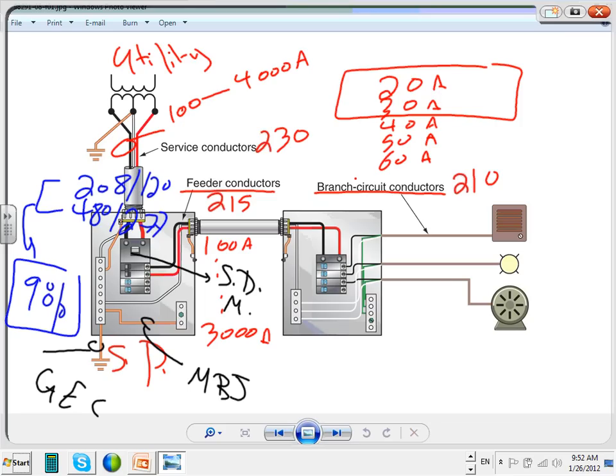You have to have a main when you bring the power to your building. I don't have to have a main here, guys. As a matter of fact, there is no main here. Can you see on the sub panel? You don't have to have a main. But at the service panel, you must have a main. You must bond the neutral to the ground, and you must provide a grounding electrode conductor. Remember that. I know we did this, and we will continue to do it, but this summarizes everything that we do for any building.